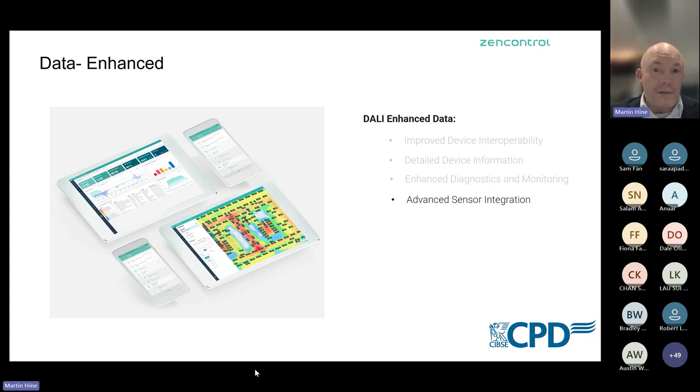We've got increased sensor information, so with environmental sensors and the air quality sensors and general multi-sensors, we can get all of this information now. We've now got additional features for the energy management, so utilising the latest DALI 2 drivers, parts 251, 252, 253. We can get real-time information from the drivers. We've also got the enhanced control features.